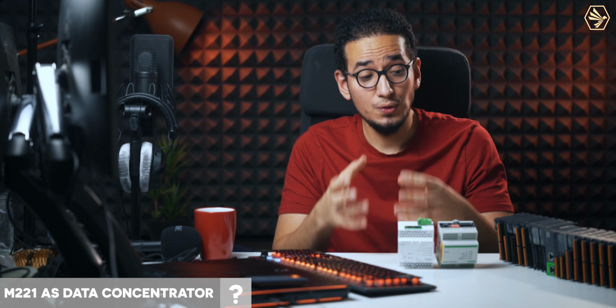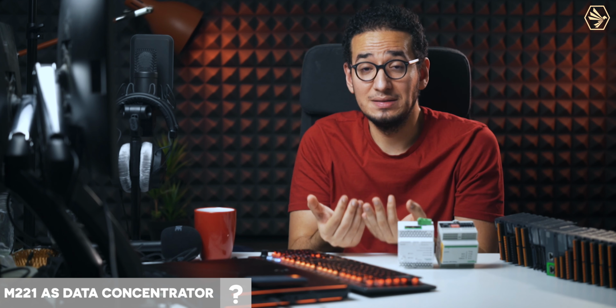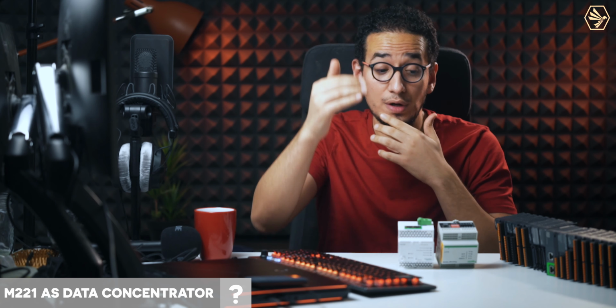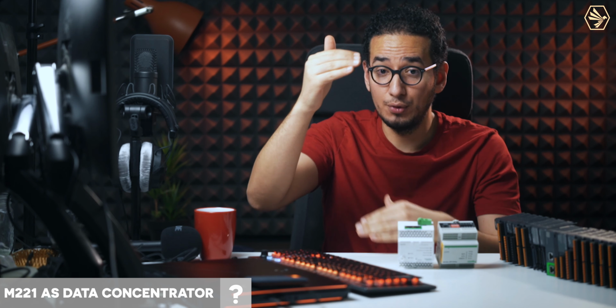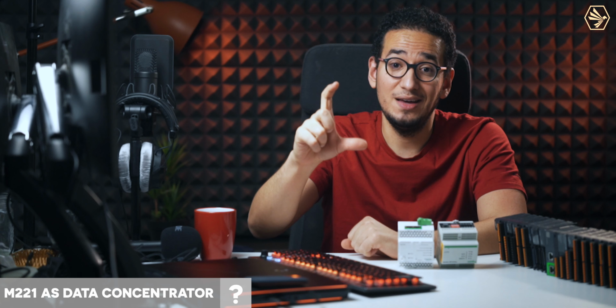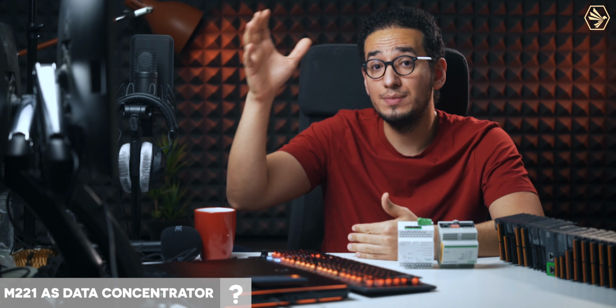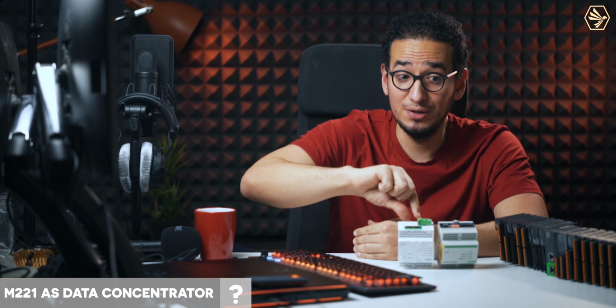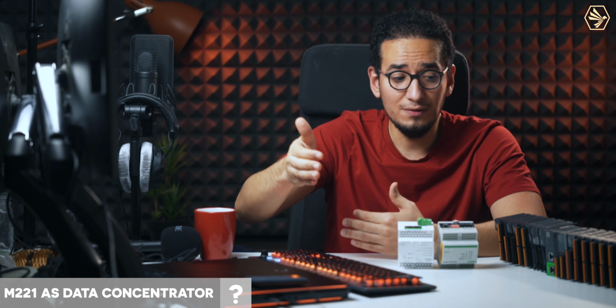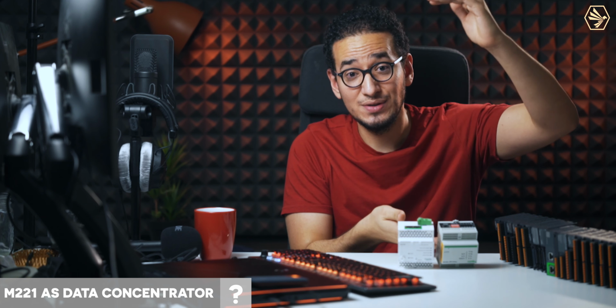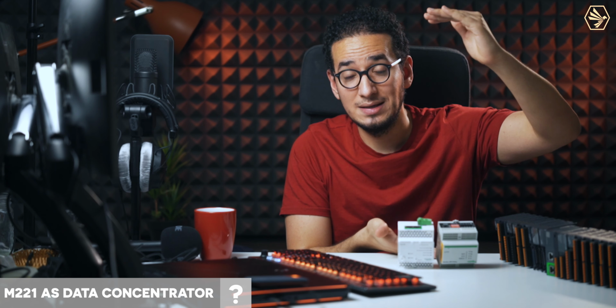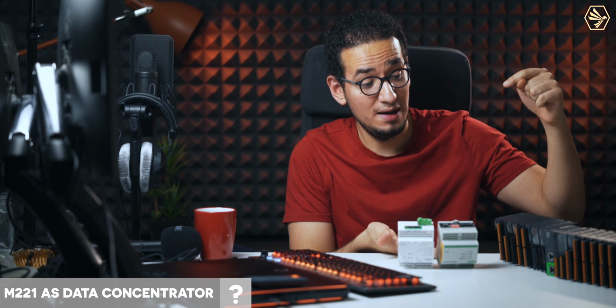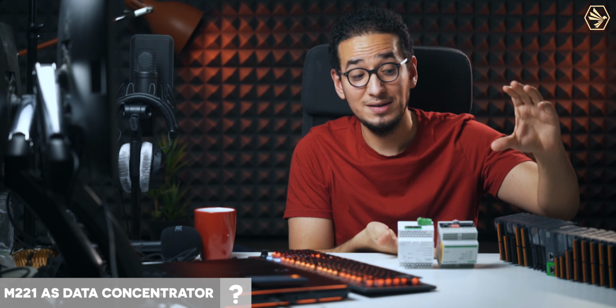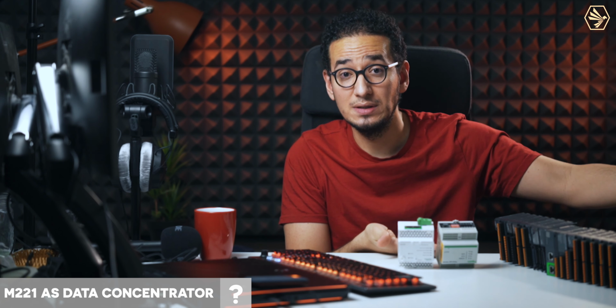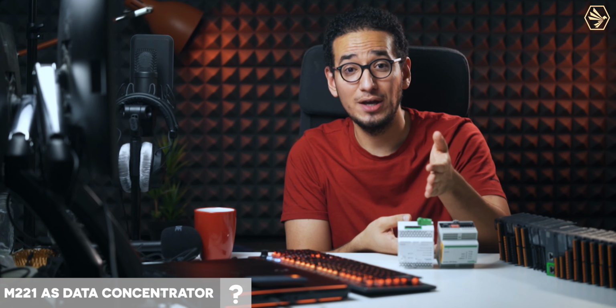So using the M221, because it's a PLC, you can rearrange or remap this data in a proper sequence. So you have only 10 addresses, and rather than the master PLC having 2 connections per device, if you have like 5 devices, you can rearrange this data in a sequence. So the master PLC will have 1 connection optimized for these 5 nodes, which will minimize, as we said, the communication load on the CPU or the master and on the network as well.